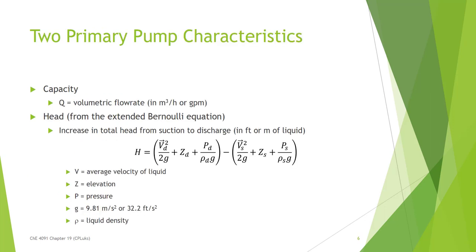There are a lot of pump characteristics that make a difference, but the two most important are capacity and head. Capacity is the volumetric flow rate, normally in gallons per minute or cubic meters per hour for a compressor. Head comes from that extended Bernoulli equation, and it looks at the change from the suction side to the discharge side of the pump.